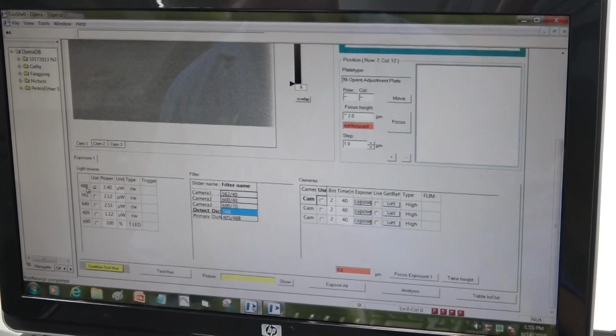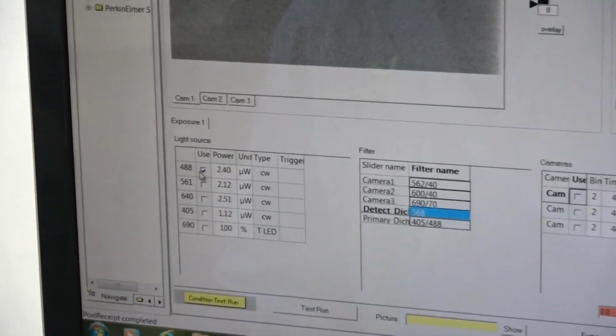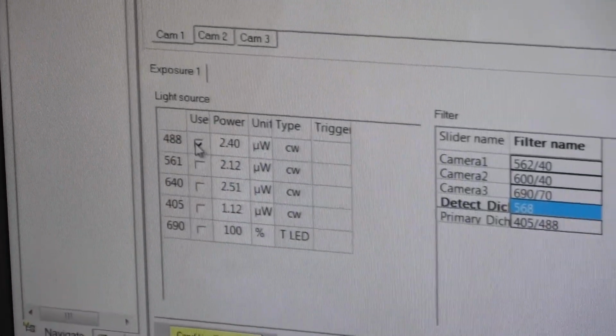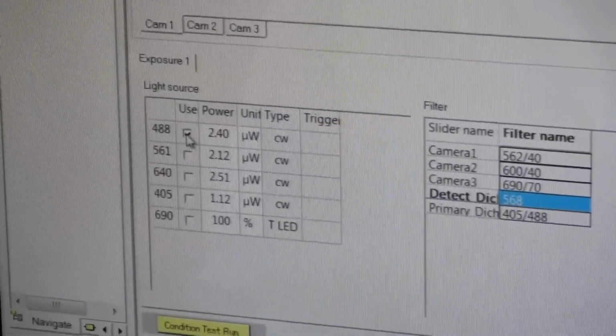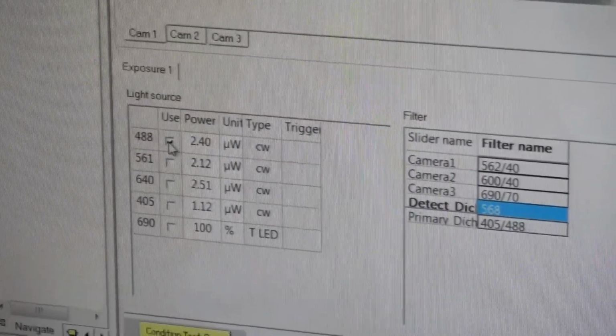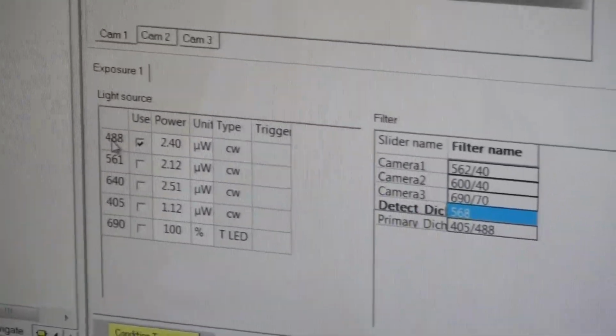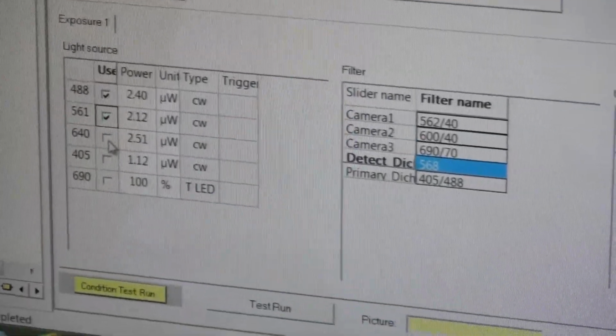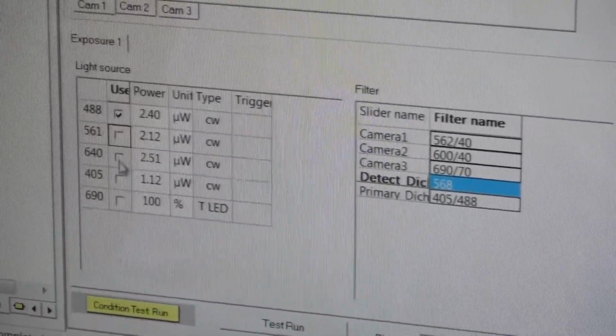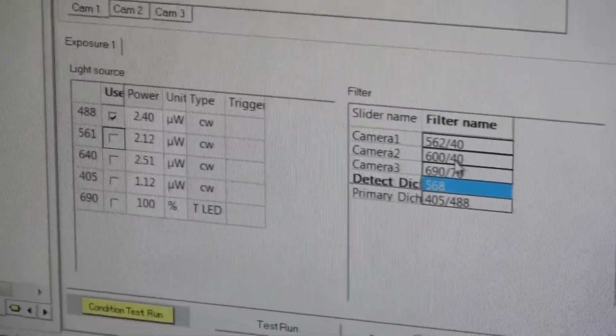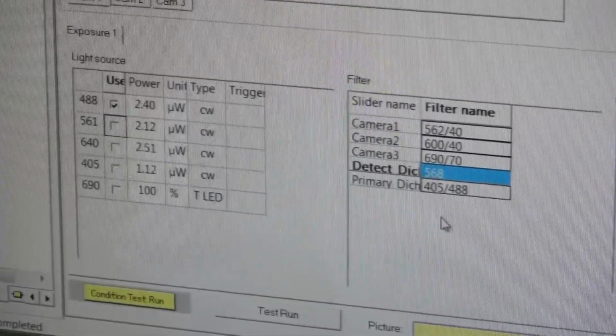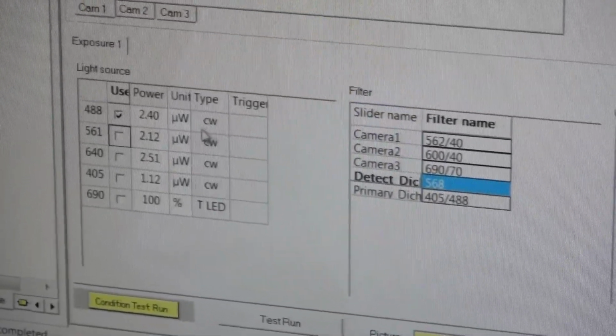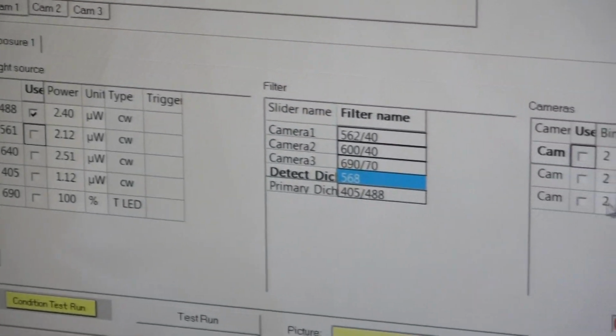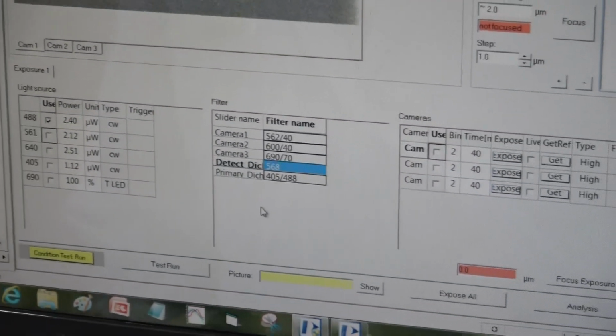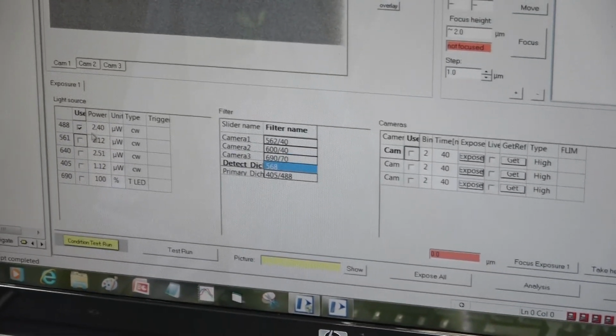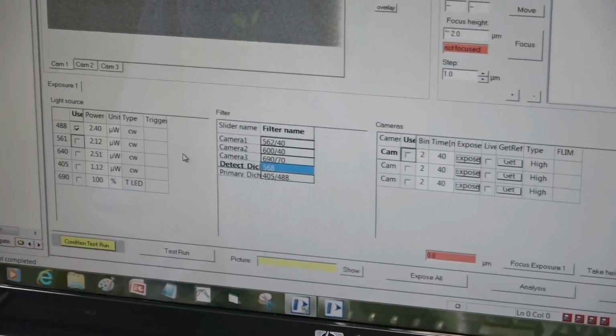Over here you can see again the lasers. This is actually where you can turn the lasers. They're technically on, but you can actually allow the lasers to come into your sample. Right now I'm only using the first laser, the 488, for demonstration. I can turn them all on, but by turning these lasers on and you don't have the right filter combinations, it tends to give you some issues and errors. So the lasers, the filters, the cameras all have to be coordinated so that they correspond with one another. So right now I'm just going to use the 488 laser for an example.